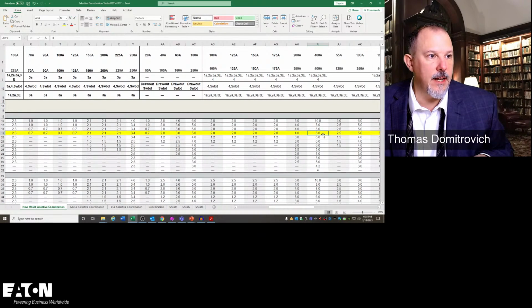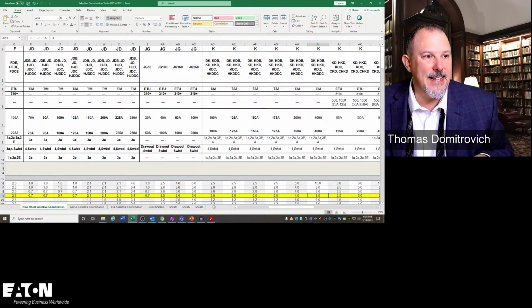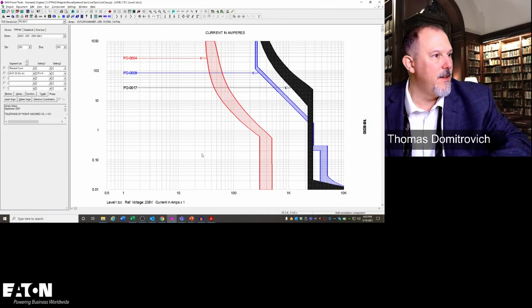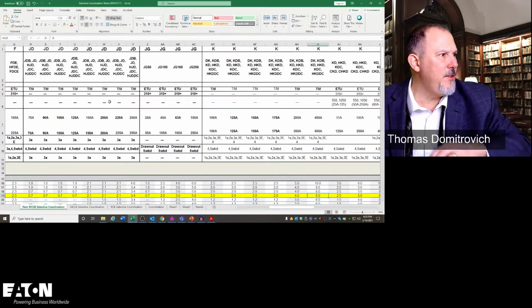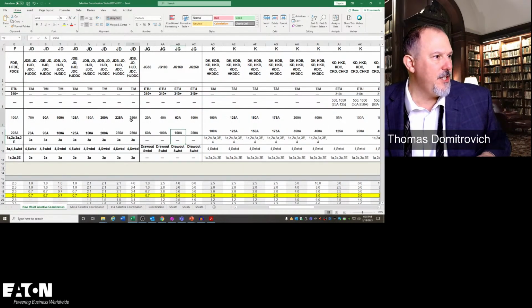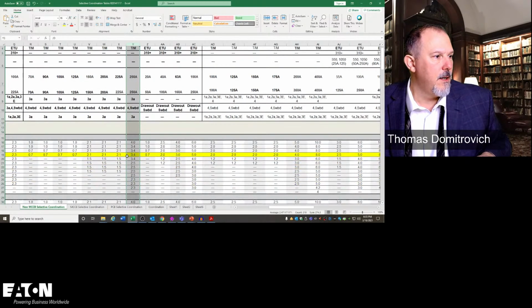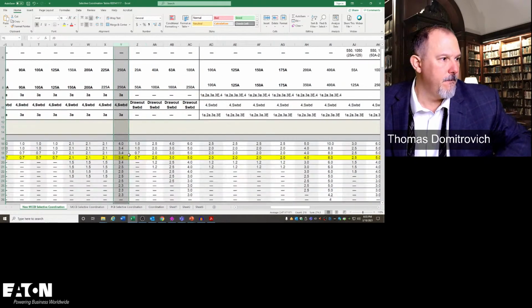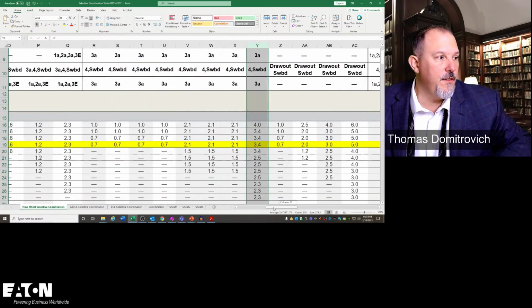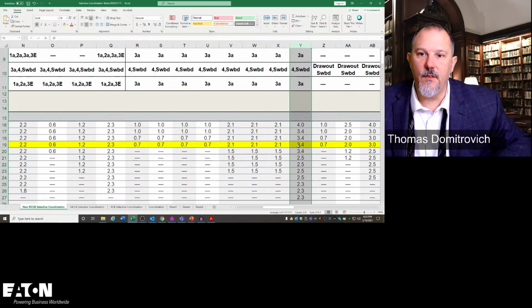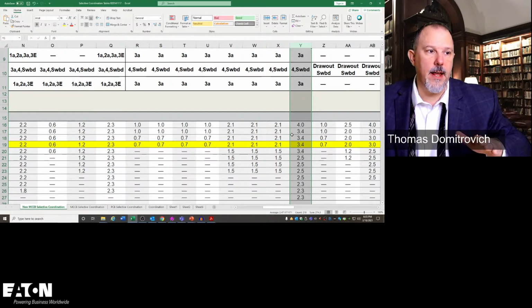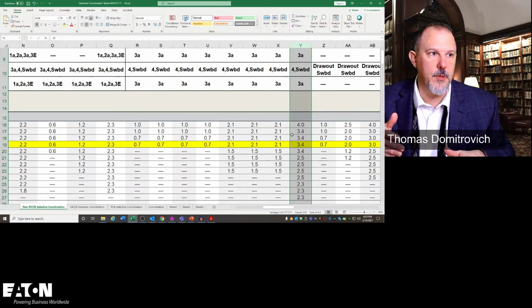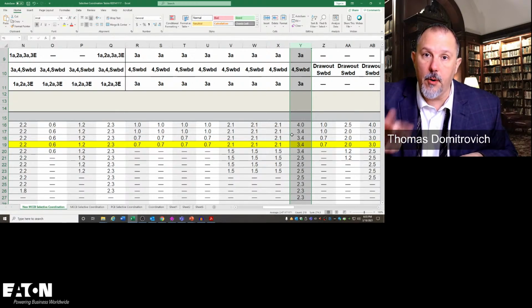There's my 8,000 amps. And that is a KD 400 amp breaker. I don't want a KD. Where's the JD? What do I have? I have a JD what? JD 250? Here's my JD 250 right here. Look what that tells me. My JD 250, 3,400 amps. Anything greater than 3,400 amps, and I will open both breakers.